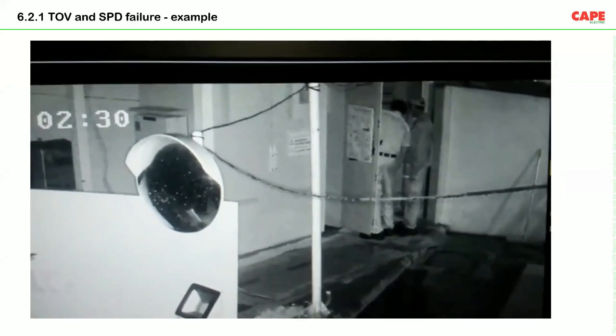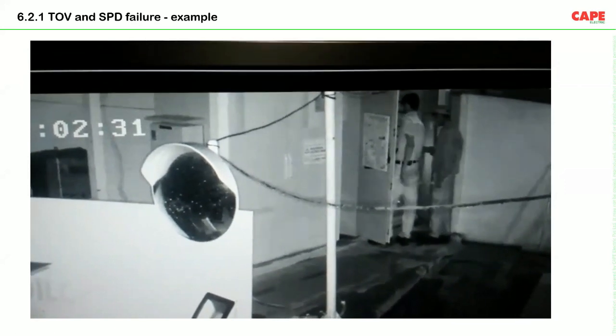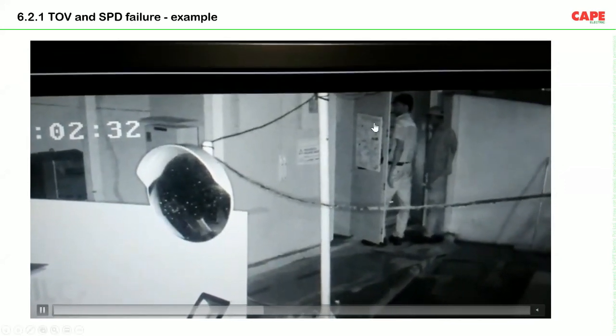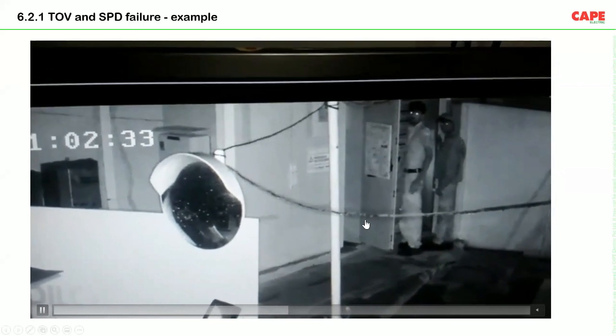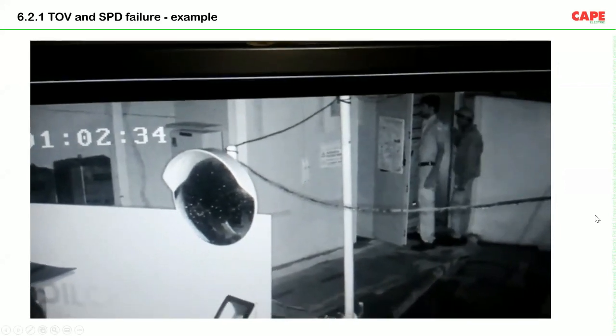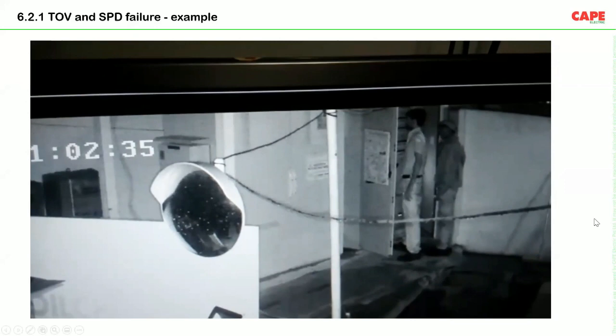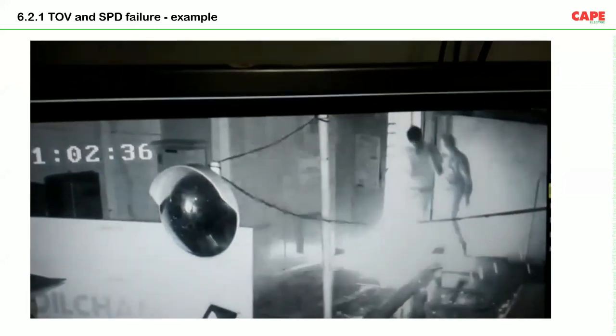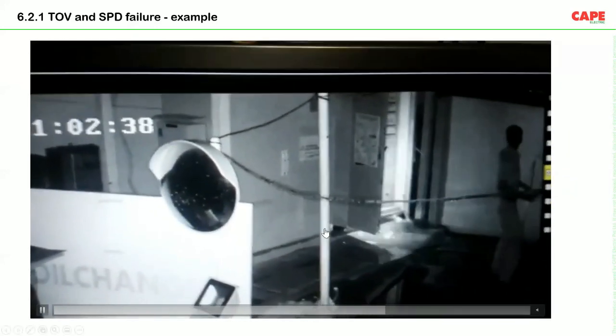some of the protective device disconnected, and there was no supply. And this gentleman, without understanding that there is no neutral, he switched on the incoming panel board, or he's asking someone to switch on the incoming panel board, and the SPD exploded.